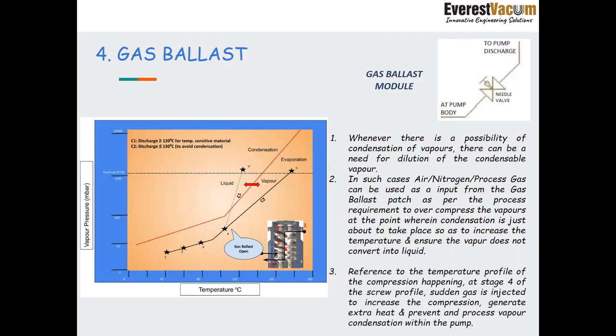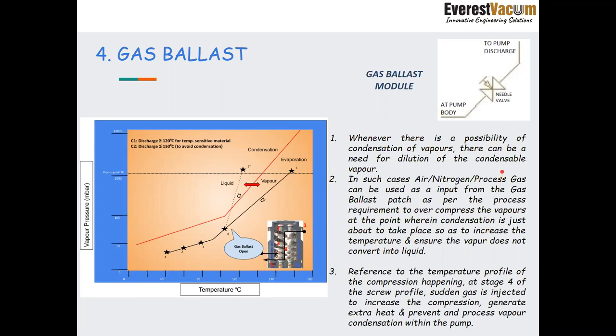So now referring to this diagram, at stage 4 of this screw profile towards the discharge, sudden gas is injected, which increases the compression, generates extra heat, and prevents the process vapor condensation within the pump. So this is the basic purpose of gas ballast, to avoid condensation inside the pump.